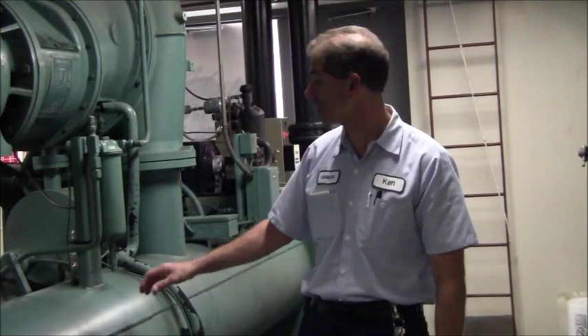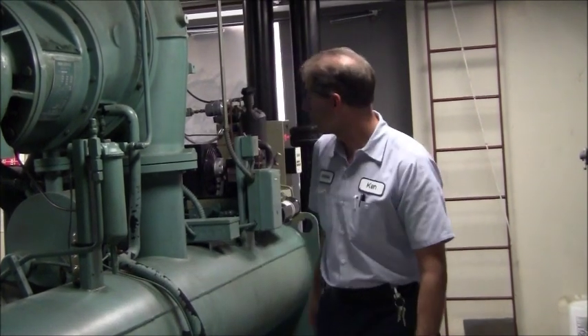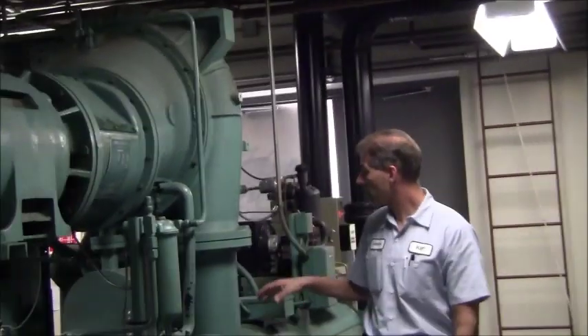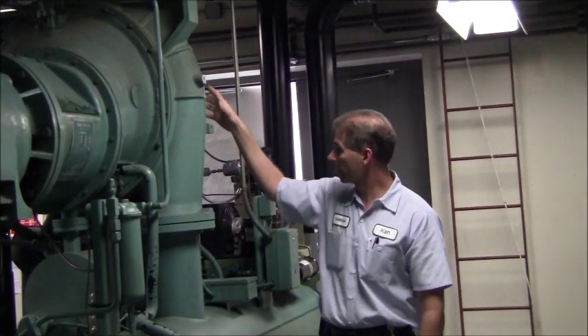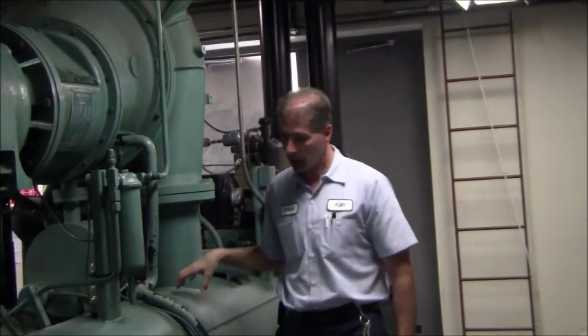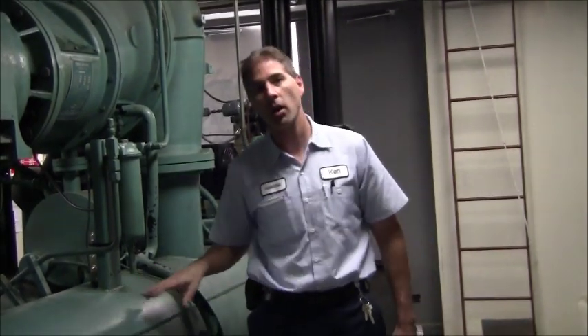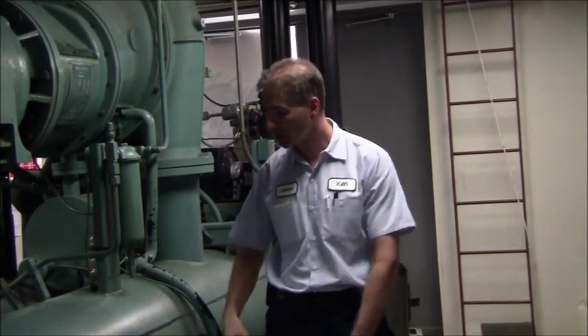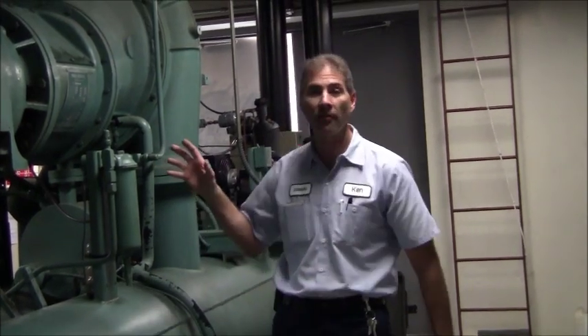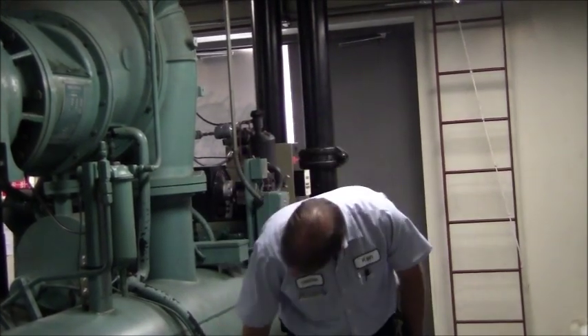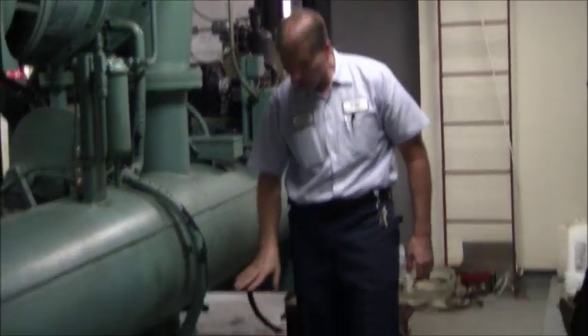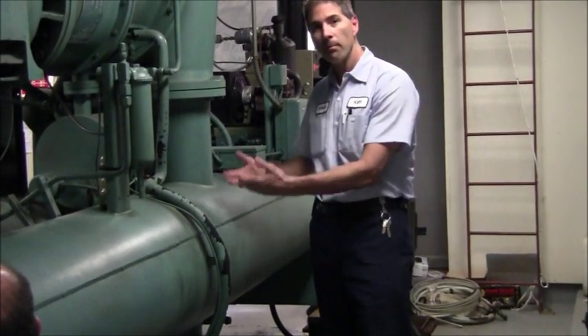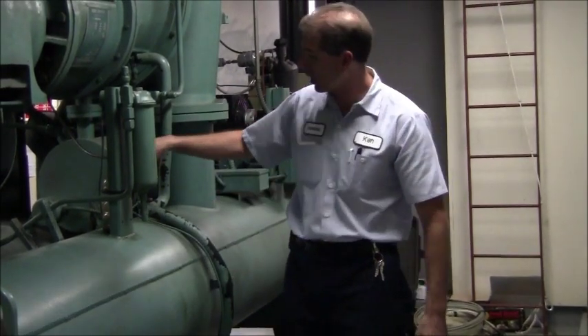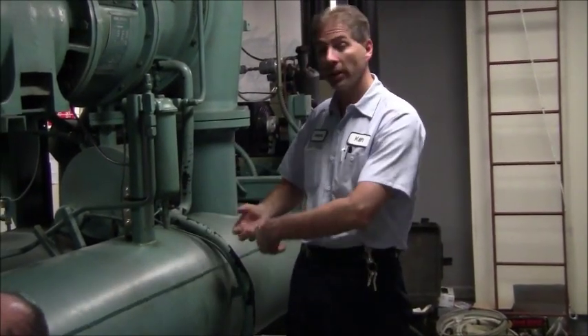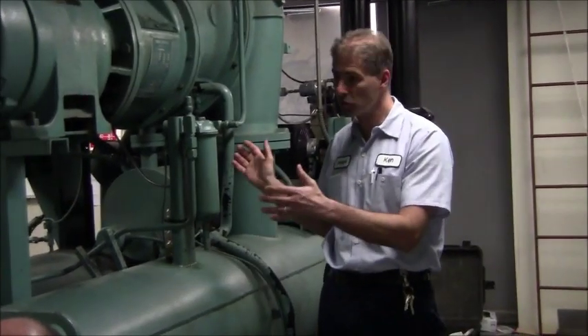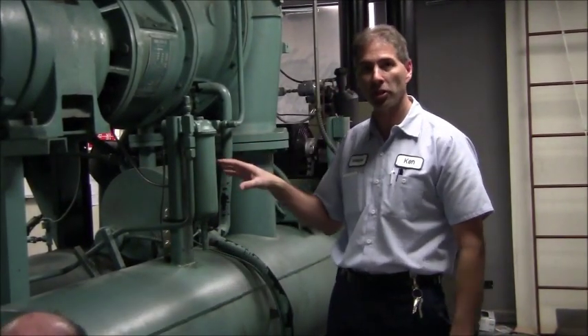All right, so here's an explanation of the refrigerant flow in the chiller. What happens is the refrigerant comes out of the compressor and it goes down into the condenser. The condensing water, which is in the tubes of the condenser, will allow the refrigerant to condense from a vapor to a liquid, which is collected here at the bottom. Then it goes through a metering device, where at that point it enters into the evaporator section, where the liquid refrigerant will boil off due to the water passing through it, the chilled water.